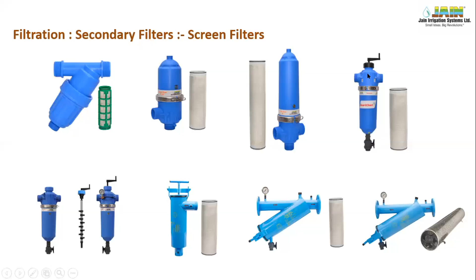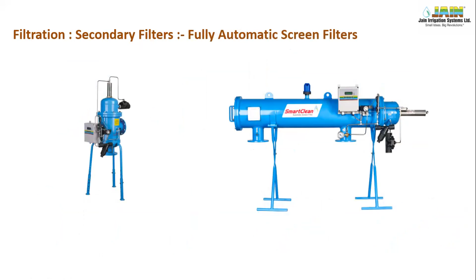In manual filters we have to take the screen element out, but here we do it with the help of automatic arrangement. When the system is running, if the pressure differential is more, the controller will detect that there's more pressure difference between inlet and outlet, meaning the screen is clogged. In that case, it will automatically start the cleaning.